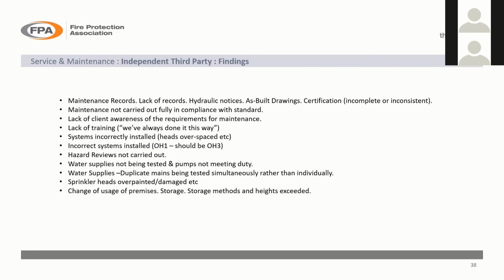In warehouses, it's quite common that where you've got beam pallet racking, for example, the beam pallets will be moved up a couple of notches on the uprights, which means that the sprinklers running down the central flue spaces are no longer in the correct positions and would be ineffective in the event of a fire. So that's the kind of thing you need to look out for. And obviously, I gave you an example earlier on where they put new partitions up. Sometimes putting up new partitions means you're blinding a sprinkler, and also means that the sprinkler on the other side is too far from the partition. So you need to relocate your sprinklers. So if you do any works, obviously run it past your sprinkler contractor and get that checked out.